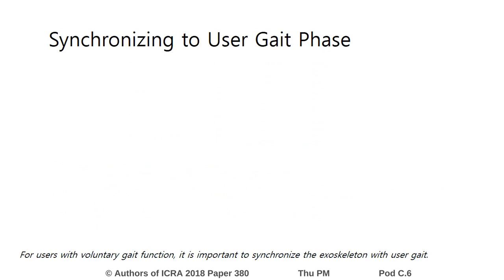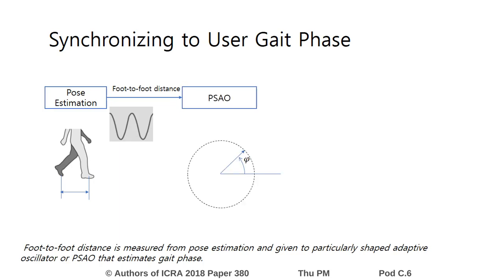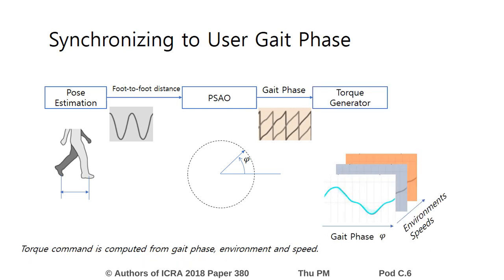For users with voluntary gait function, it is important to synchronize the exoskeleton with user gait. Foot-to-foot distance is measured from pose estimation and given to a particularly shaped adaptive oscillator, or PSAO, that estimates gait phase. Torque command is computed from gait phase, environment, and speed.